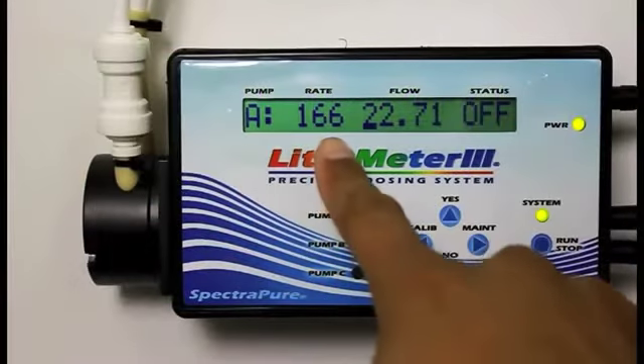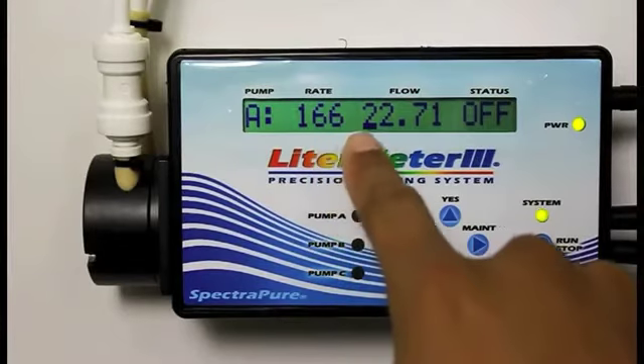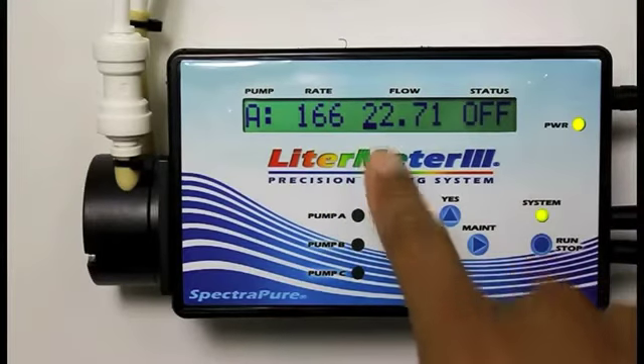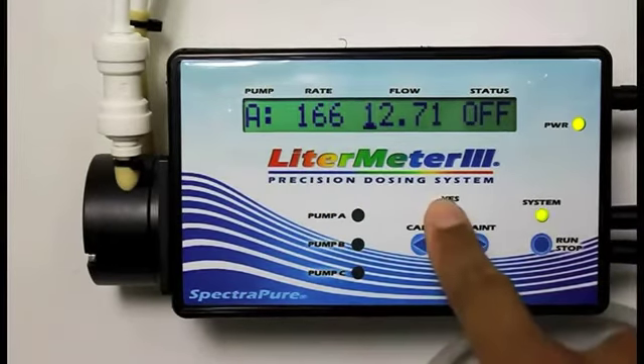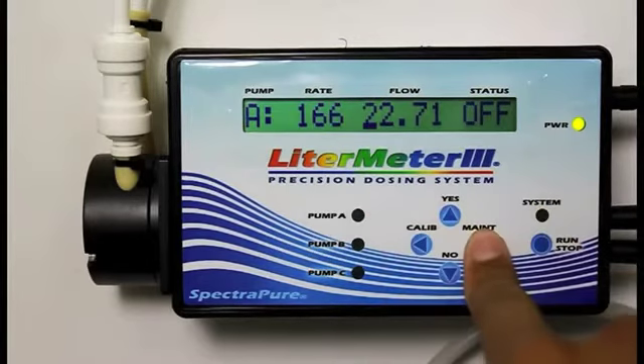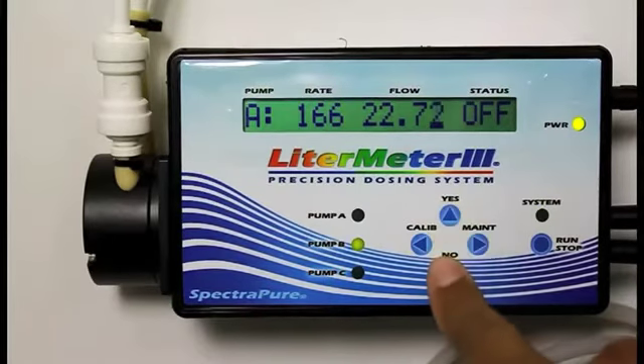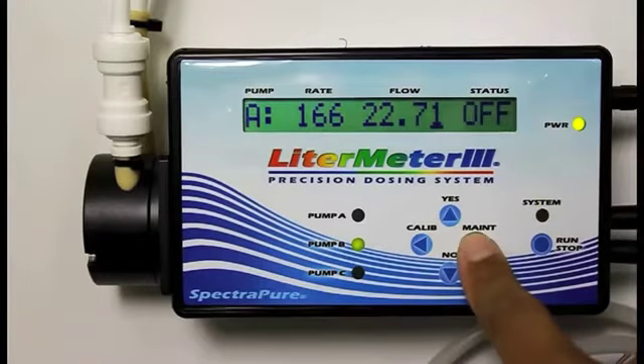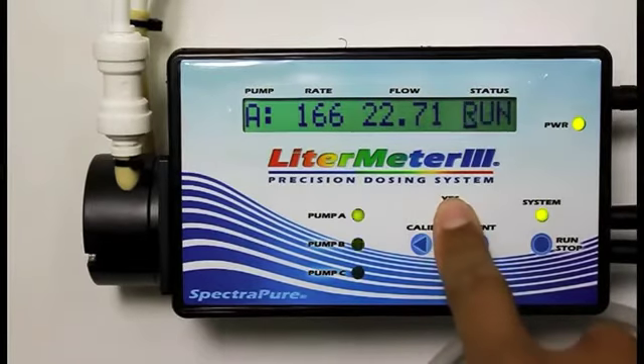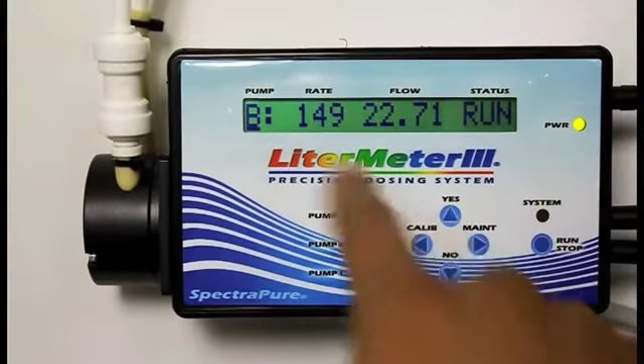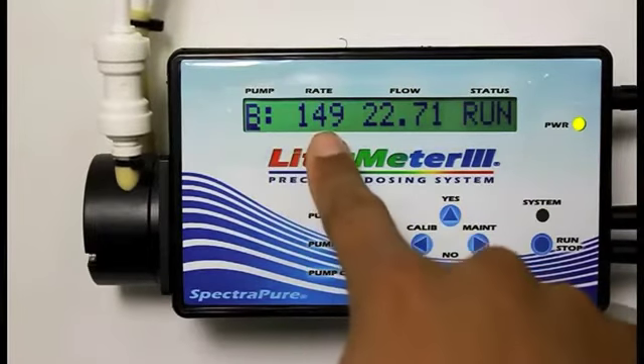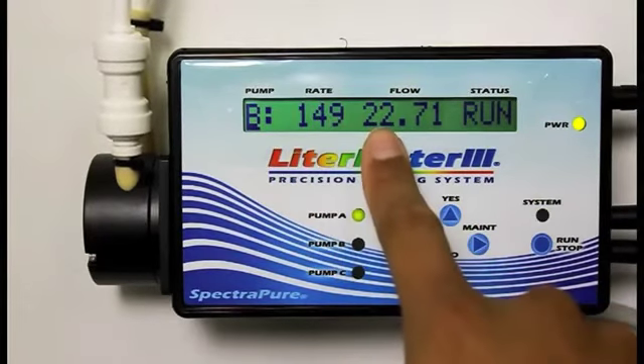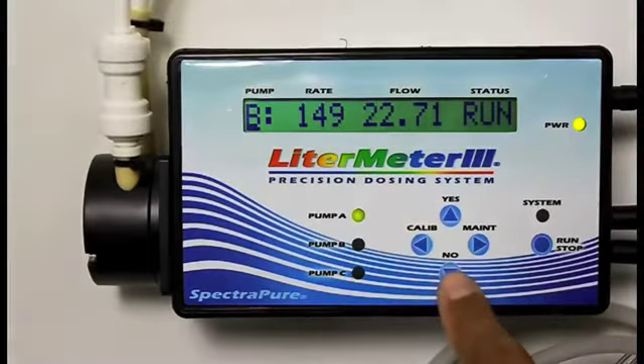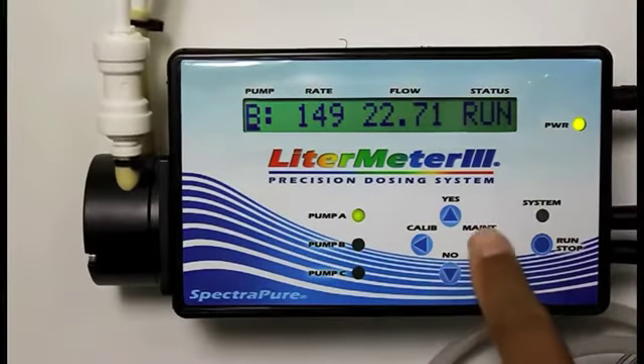At this point, we can see that this pump has a maximum rate of delivery of 166 milliliters per minute, and I've set it to pump 22.71 liters per day. Change these values by simply pressing the Up, Down, Yes, No buttons, and you can move across characters or fields via the forward, back, or calibration maintenance buttons. Repeat these steps as necessary for each pump. I like to cycle through each pump and verify the desired flow is correct and make any changes as necessary and set their status to run.